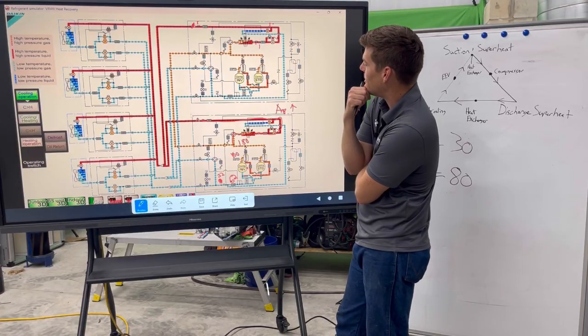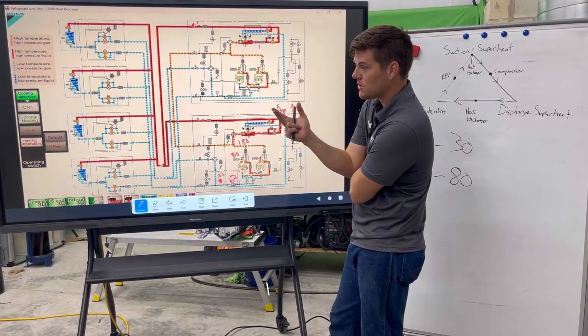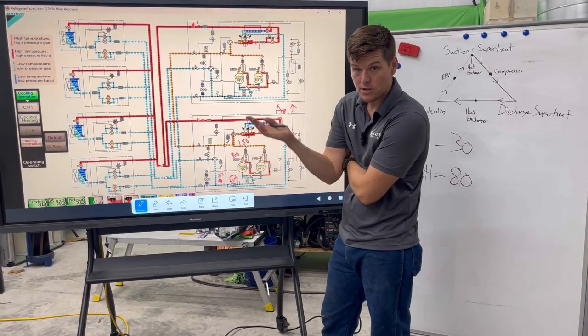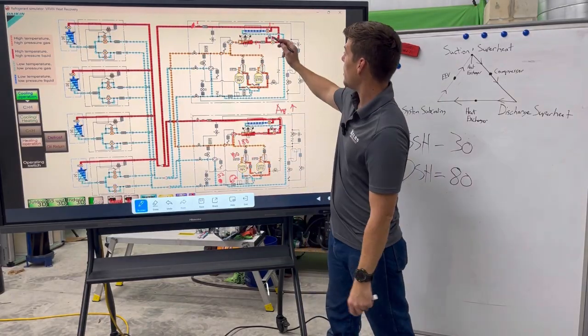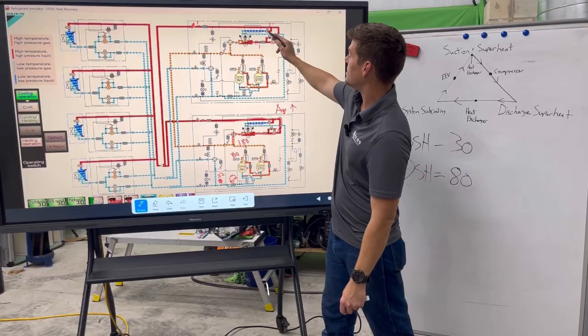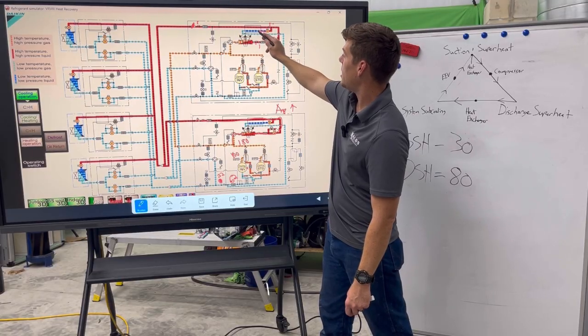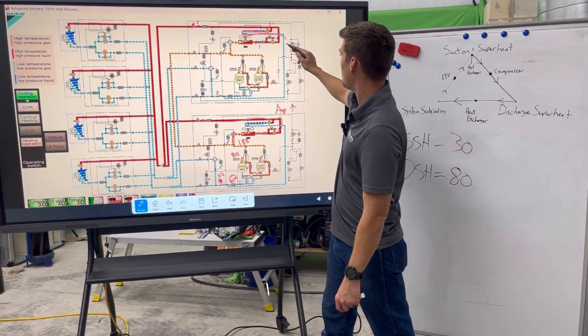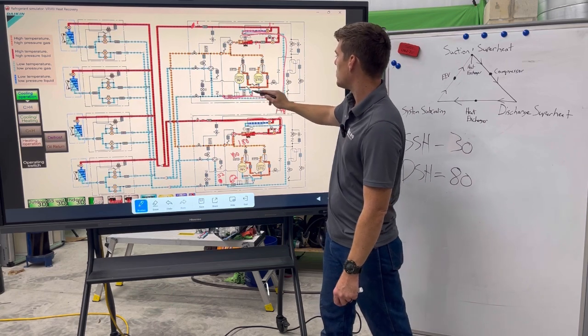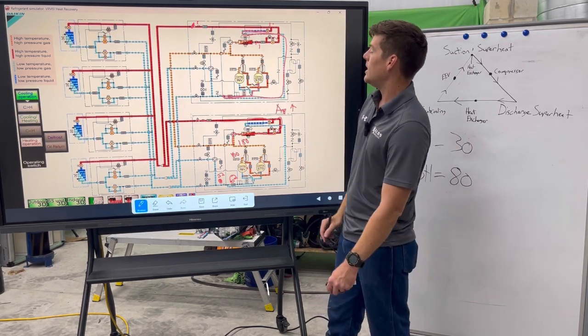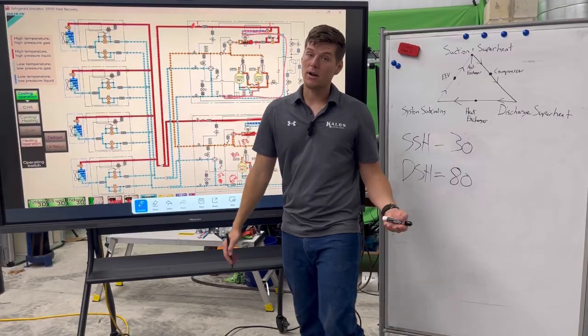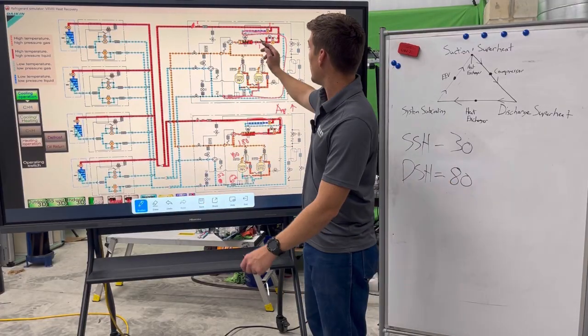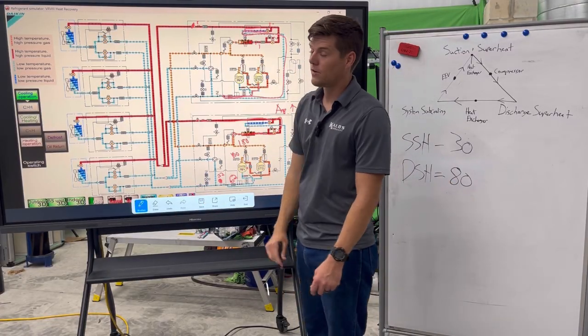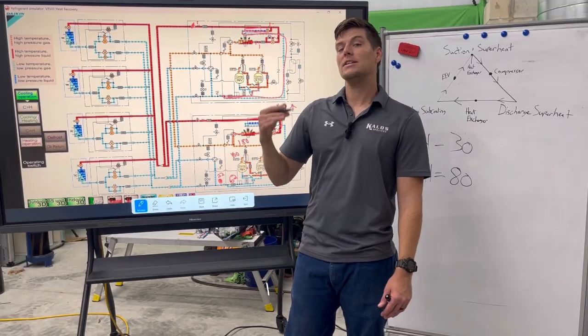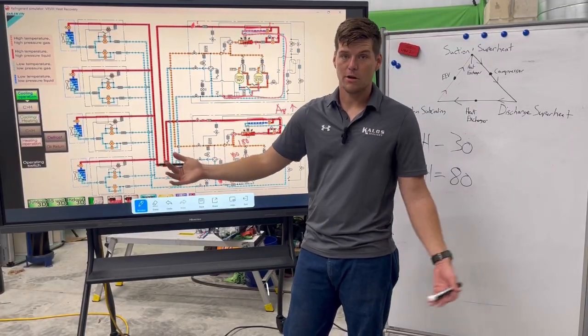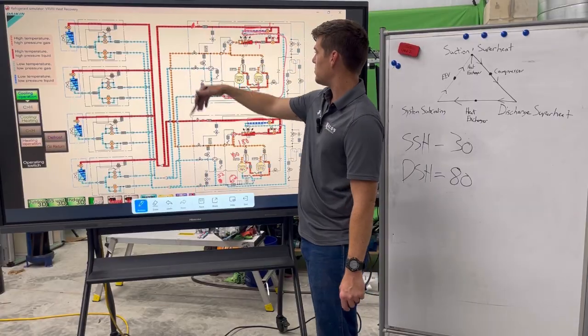So when we talk about VRF, we have something that's called a subcooler. That subcooler is vapor on demand, right? We're taking a saturated liquid, putting it into a low pressure state, we're boiling it off into a vapor, and then that vapor comes back around, and where does it go? It injects back into our suction line, back over to our compressor. It is vapor on demand. Now, its byproduct is subcooled liquid refrigerant, because again, there has to be a medium on the opposite side to transfer heat to, but its main purpose, again, is maintaining vapor to our pumps, our vapor pumps, especially when changes are taking place within the system.